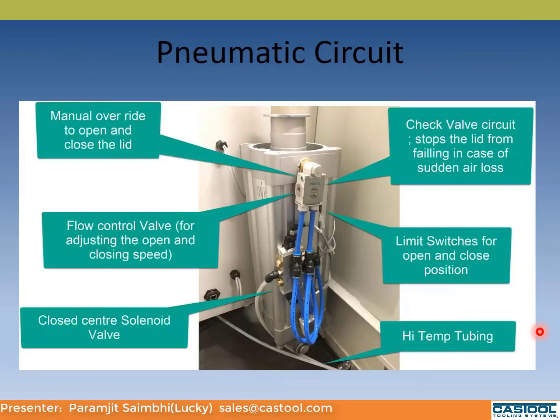Here's a setup we're showing you for the pneumatic circuit. You have the manual override here. You can press that to open and close the lid. You have the flow control valve. There's a solenoid here to open and close the lid. It's closed center. And we run high temp tubing, which is running under the oven, depending on the application. And you have the limit switches for open and close. And there's a check valve circuit. So basically, in case of air loss, the lid locks in place.